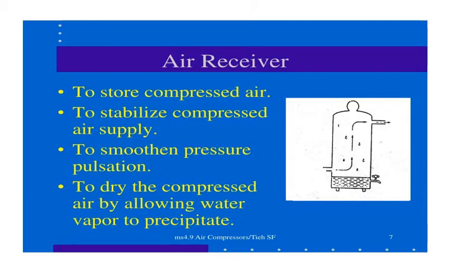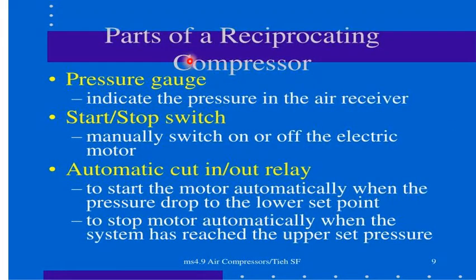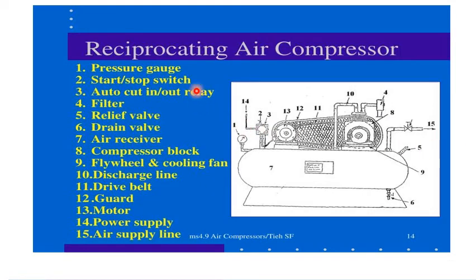The air receiver is used to store compressed air. The parts of the reciprocating compressor include: a pressure gauge, which indicates the pressure in the air receiver; a start/stop switch to manually switch the electric motor on or off; and an automatic cut-in/cut-out relay to start the motor automatically when pressure drops to the lower set point and stop it when the upper set pressure is reached. Other components include an air filter and a relief valve.